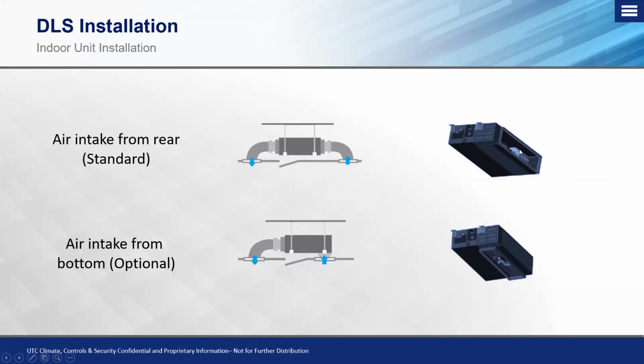So essentially you're taking this, putting it on the bottom, and taking this cover plate and plugging up the top. Okay, so this is really nice, especially for apartment style applications, where you can set up a removable grill to access where your filter is and also access where your fan motor is on the bottom side. One thing to keep in mind when you're suspending these units, you want to make sure that you leave enough clearance on the bottom side, especially on the horizontal style installations, where you can access your fan motor in case you need to get back there to clean a wheel or if a motor decides to fail.